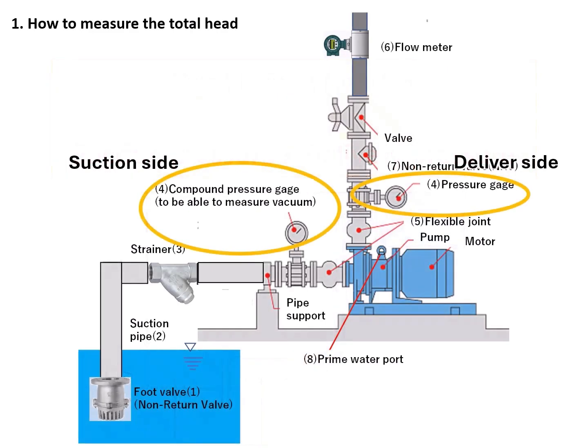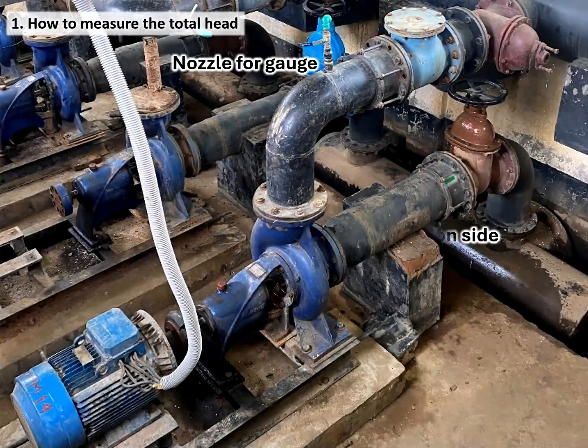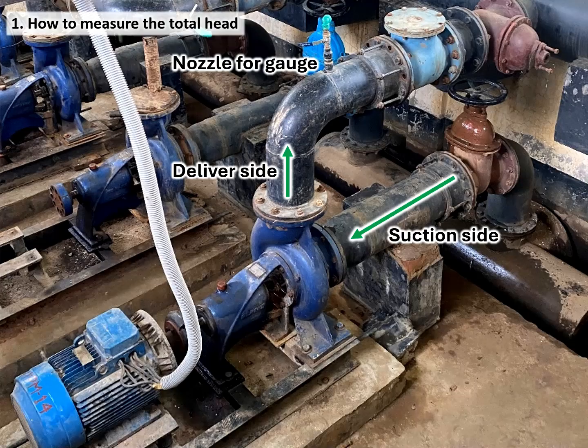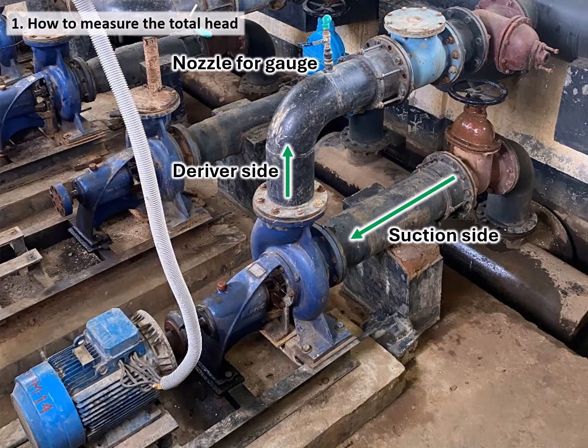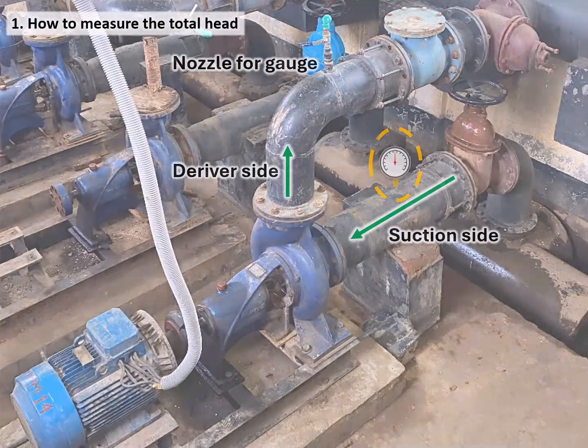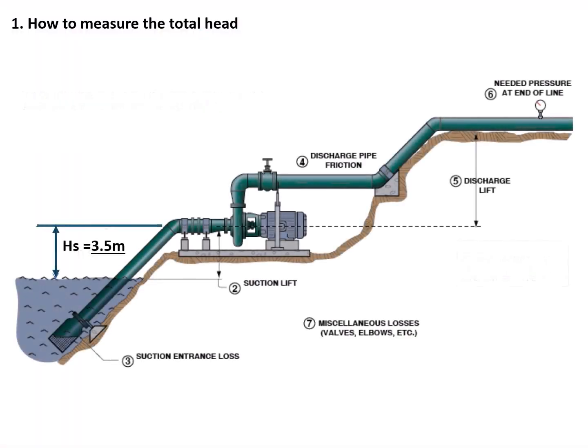In the case of an on-land pump, the pressure on the suction side is always negative because water is pumped up by vacuum pressure on this side. When calculating total head, the absolute value of suction pressure shall be used. This is showing the example of an on-land pump at the water treatment plant. In the field, you might see the pressure gauge is not installed at the suction side, as in this picture. In this case, the pressure of the suction side can be calculated by the elevation gap from the water level to the pump.